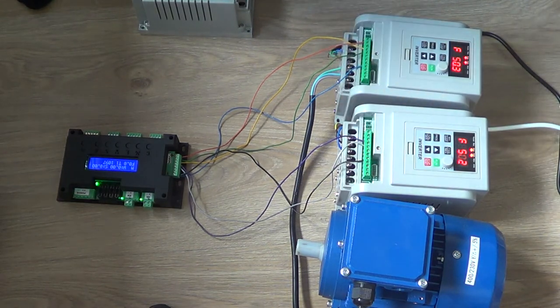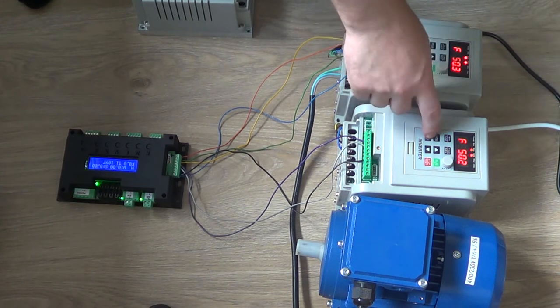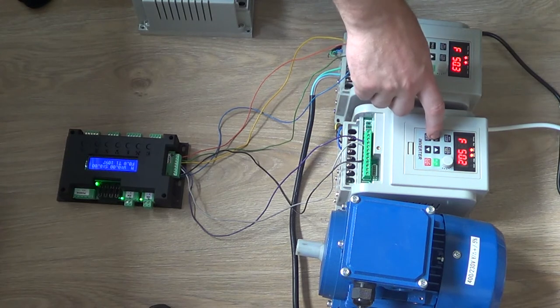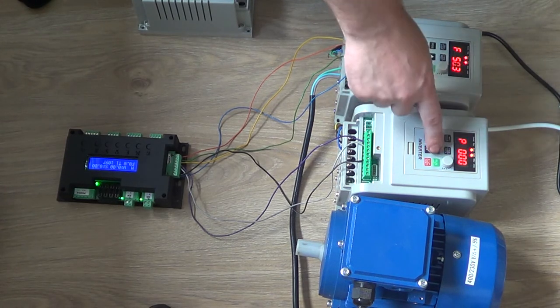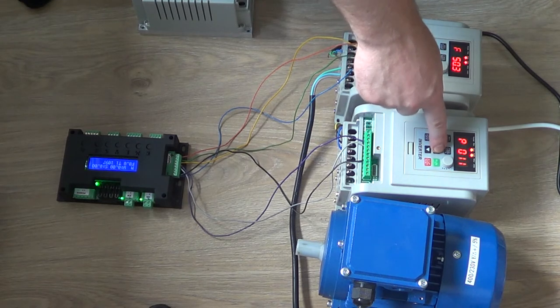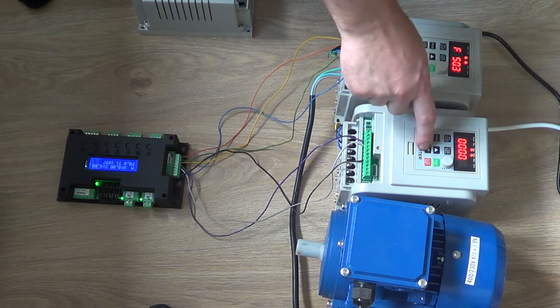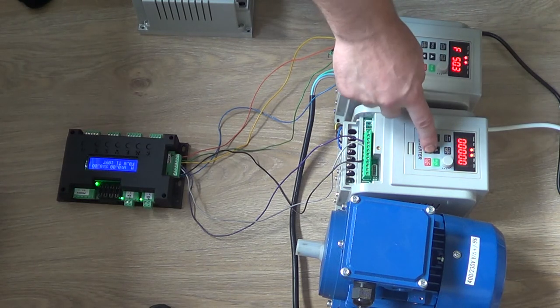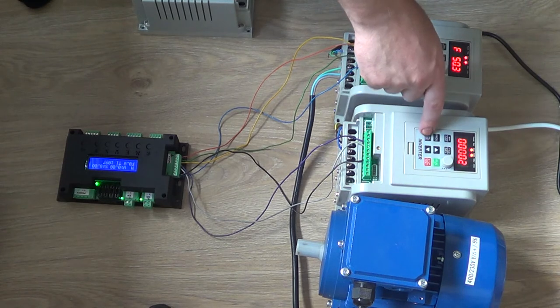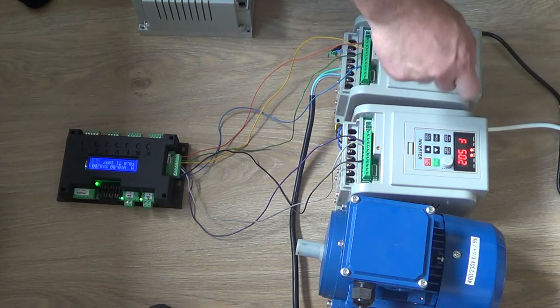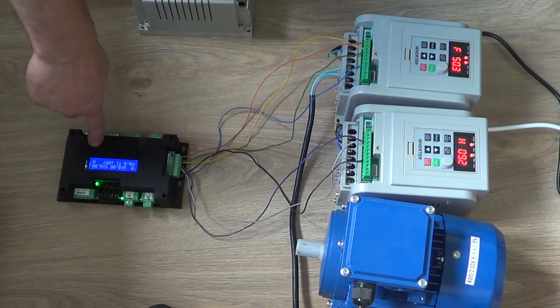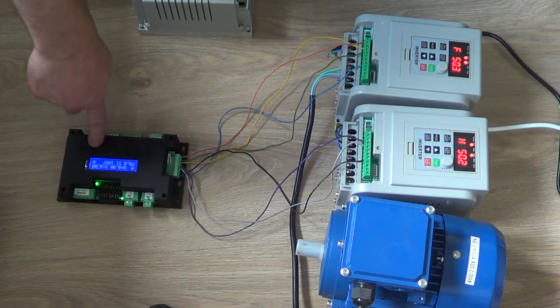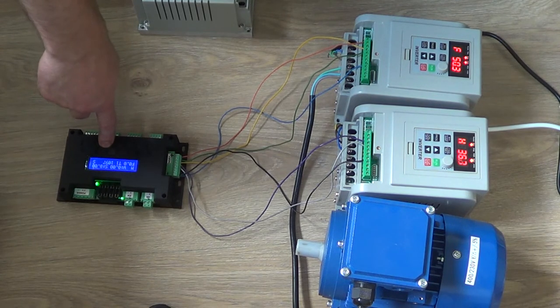But of course I don't want to do it manually. If I will, I'll just change the parameters. So I have to change the parameters. And I'm going to parameter 11. Okay and just switch this position from 0 to 2 and then just program it. And from now it will be responsive. In both directions of course.